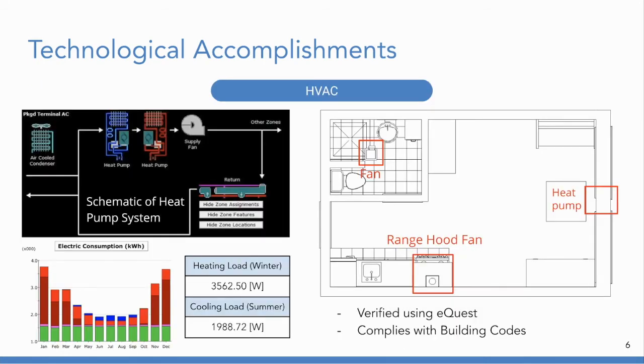Furthermore, we designed the HVAC for our unit. For the unit's HVAC, we have selected a heat pump system to heat and cool throughout the year. The calculated heating and cooling loads for one unit are 3,562.5 watts and 1,988.72 watts respectively. Our estimated loads were verified using eQuest, the monthly energy consumption, and the system schematic, all shown on the left.